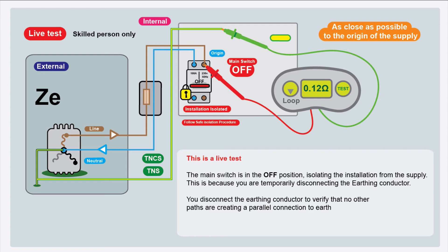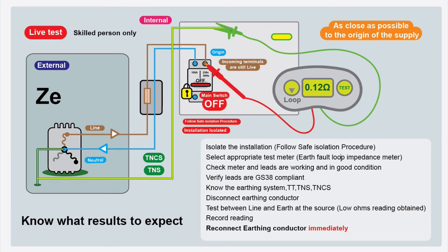We're ready to do our ZE test. This is a live test — the main switch is off, isolating the installation from the supply, because we are going to temporarily disconnect the earthing conductor to verify that no other paths are creating a parallel connection to earth. This is a live test which should only be done by a skilled person, but during training you'll be assisted by someone with the relevant skills and knowledge. So first, safe isolation — check that everything is switched off before disconnecting the main earthing conductor.